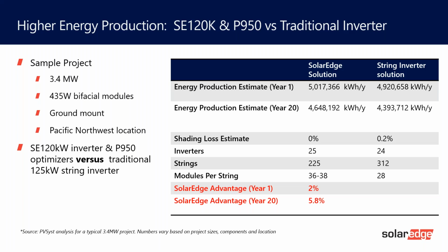So here you can see everything we talked about: we produce more energy in year 1, about 2%, almost 6% more by year 20. That's an average of about 4% a year on a site that's essentially flat with no shading, and even versus a 1500 volt string inverter, we still had longer strings and therefore fewer strings.